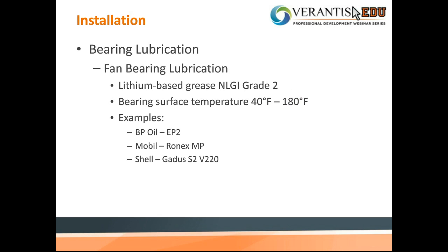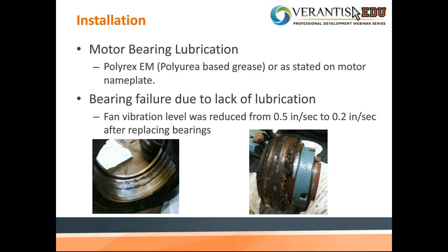So with installation, we want to make sure the bearings are lubricated properly. So fan bearing lubrication, it is typically a lithium-based grease, so an NLGI grade 2 style of lithium grease. Bearing surface temps can reach anywhere between 40 degrees Fahrenheit all the way up to 180, and then some. A couple examples are BP Oil EP2, a Mobil Ronex MP, and then Shell Gadus S2 V220. These are all great styles of lithium grease that we've seen in the field. And then motor bearing lubrication, this is typically a polyurea-based grease, like a Polyrex EM, or something that is stated on the motor nameplate itself. Typically the motor will have exactly what type of grease is noted on the plate.